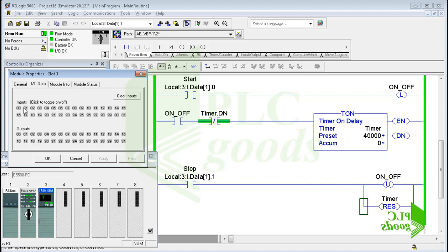As you see, if I press the start and stop digital inputs simultaneously, the stop request will have priority over the start request. Although the processor decides to activate the inserted timer in the first and second rung, its final decision is to reset the timer and clear on underscore off memory, in the last rung.